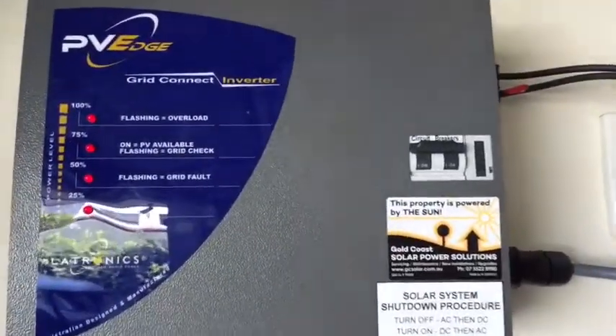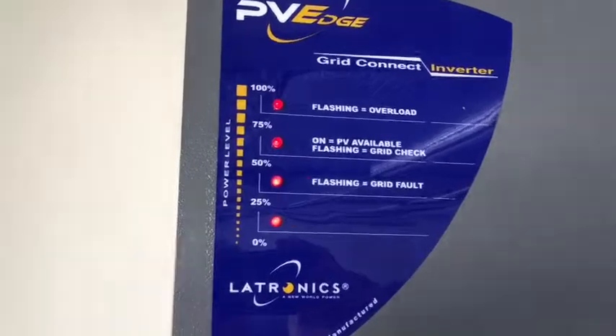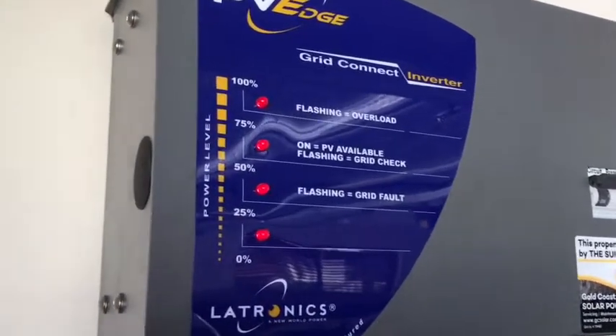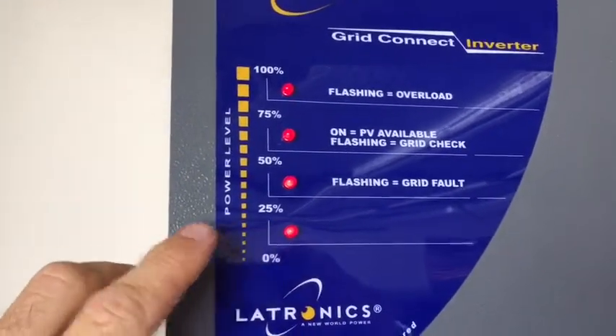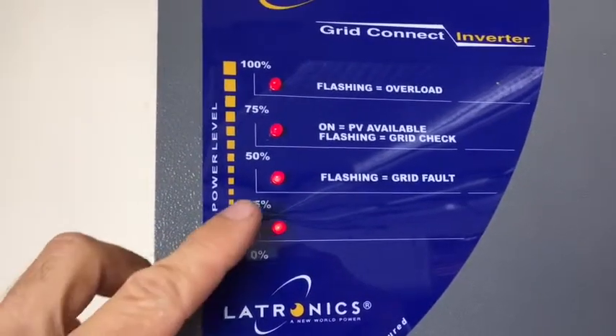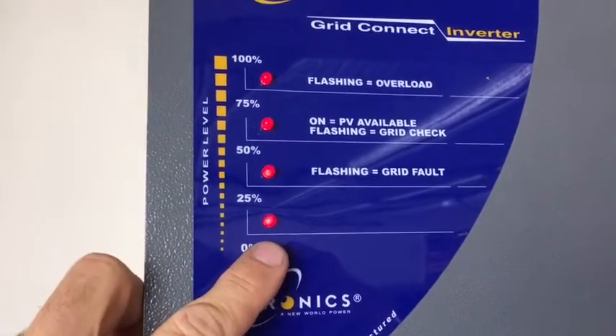Here we are again and we've replaced this circuit breaker with a good quality replacement unit. You can see that the inverter is working at full capacity — all four lights are on. With the Latronics inverter, it's always important to know that if the sun's out at all and the system's working, the bottom light at least should always be on.